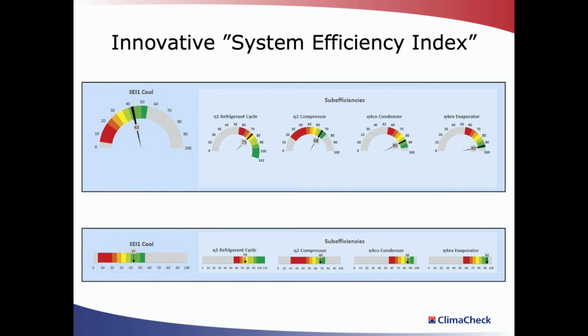The same is true of the evaporator. If it's not performing well, maybe there's inadequate airflow rate or water flow rate, then this will manifest itself in poor compressor performance and overall system inefficiency. So SEI is now available through ClimaCheck. If you have a ClimaCheck system connected to our web server, you can go online and look at system efficiency index and draw all the conclusions for the necessary corrections and service in the field before you even have to visit the site.